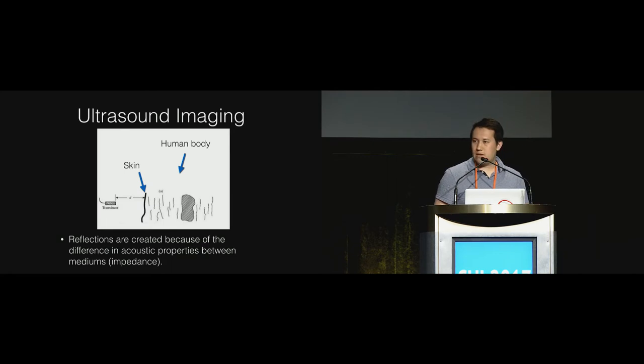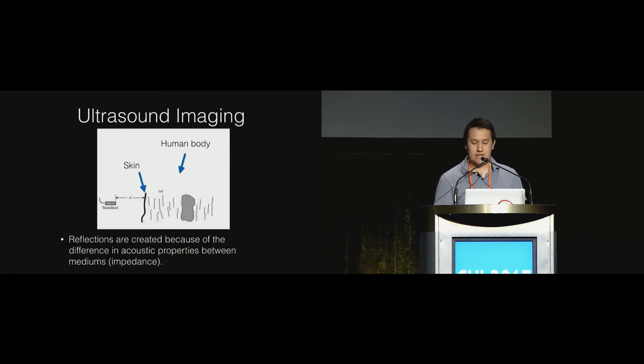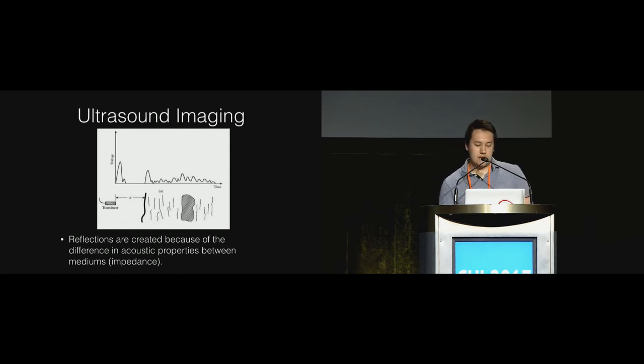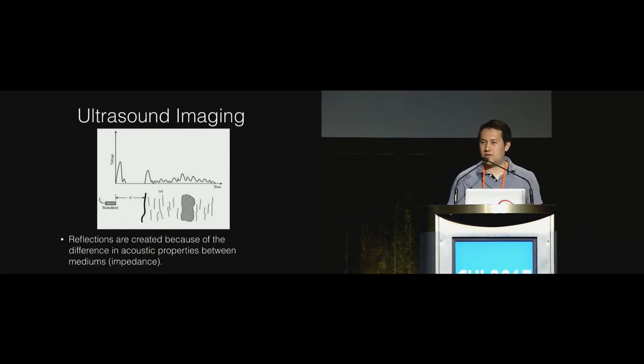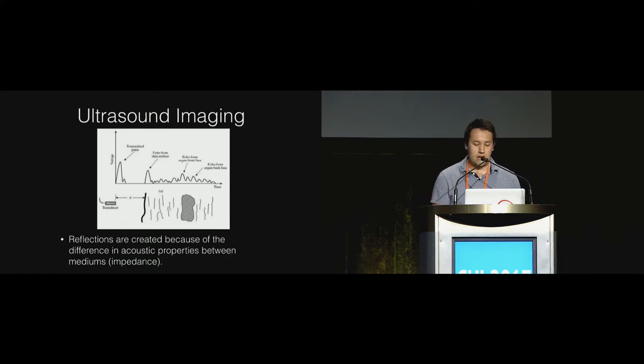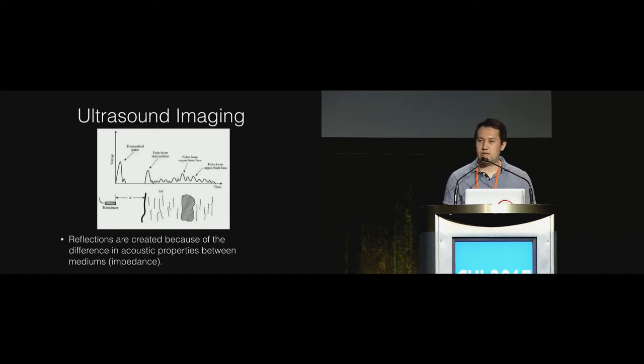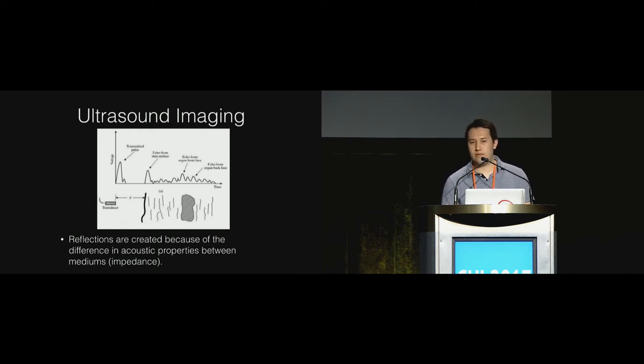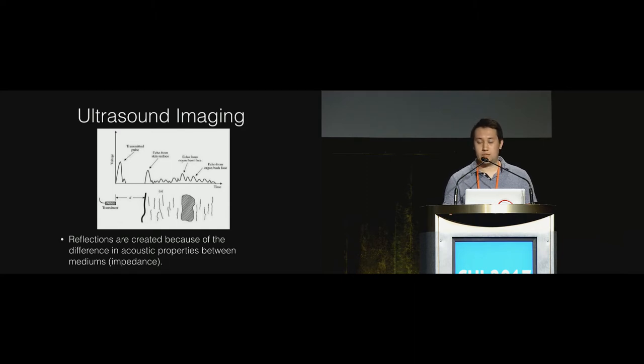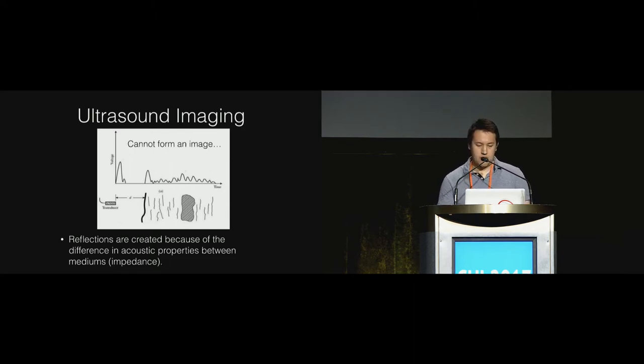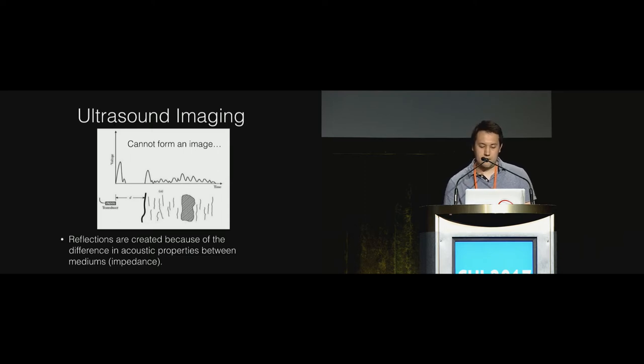Here's a more realistic situation where a transducer is pulsing sound into the human body. The graph represents the intensity of the echo received by the transducer. Peaks occur when there is a large change in acoustic impedance between mediums, so this might be for instance from bone to muscle or even between the muscle and the skin. But we can't form an image from this yet, we just know the distance away again.